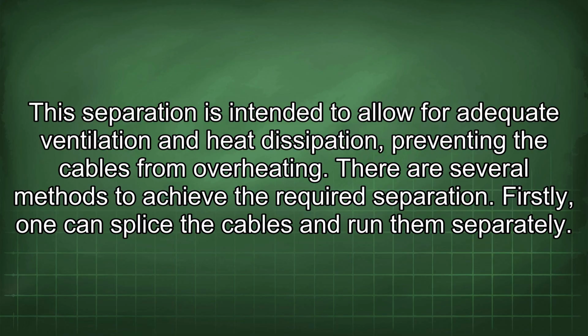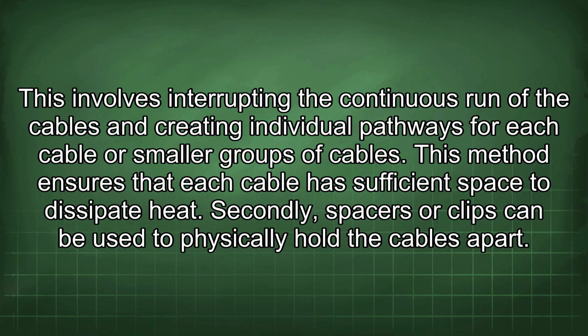There are several methods to achieve the required separation. Firstly, one can splice the cables and run them separately. This involves interrupting the continuous run of the cables and creating individual pathways for each cable or smaller groups of cables. This method ensures that each cable has sufficient space to dissipate heat.